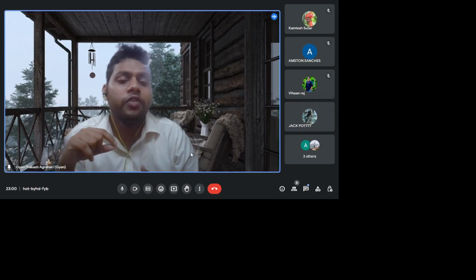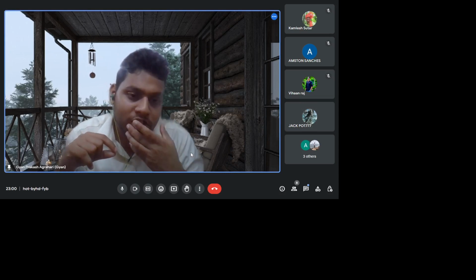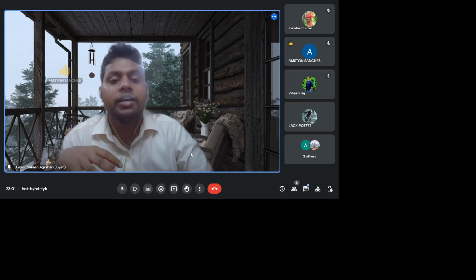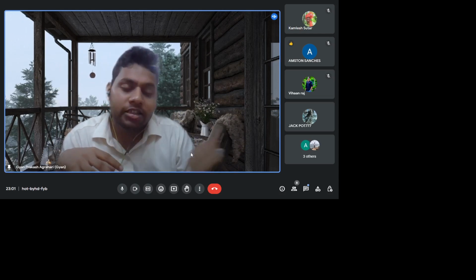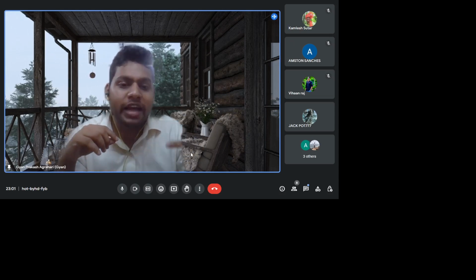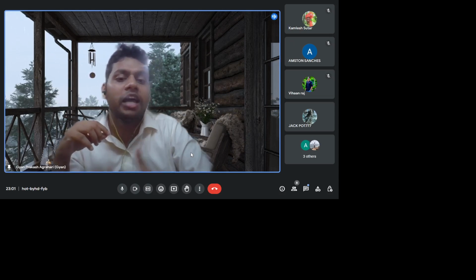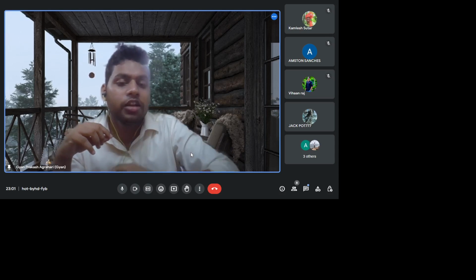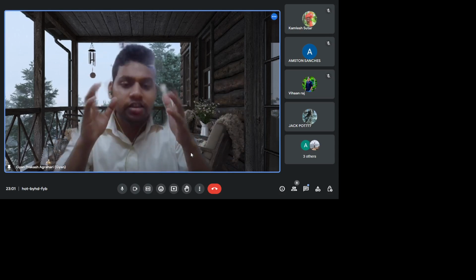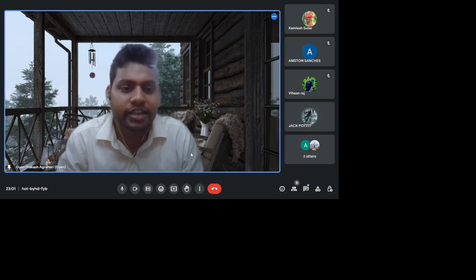Whenever the water level goes down, the temperature of the drum increases greatly, and at that time this fusible plug melts and creates a passage for the high temperature steam to escape from the boiler, and the temperature of the boiler is maintained. Now it is cleared.